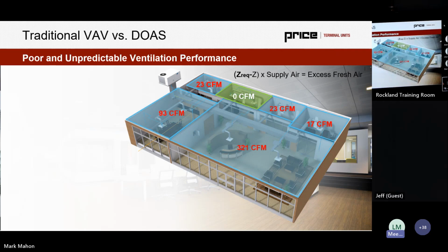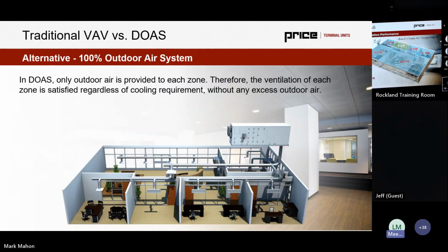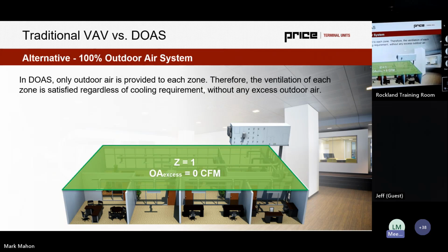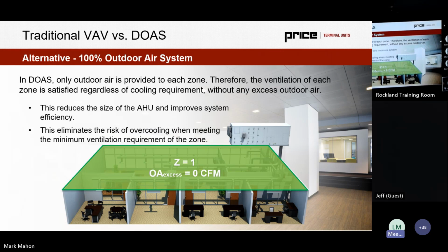Now, it's also possible instead, rather than excess fresh air, if the system was balancing correctly, you could have a lack of fresh air to certain zones. You could have a risk of maybe overcooling internal zones in this case as well. But this is ASHRAE's rationale and where it comes from. And so from their viewpoint, the alternative being 100% outdoor air, that means we're only providing outdoor air to each zone. Therefore, the ventilation of each zone is satisfied regardless of the cooling load. That decoupling of ventilation and latent versus sensible means that we can hit ventilation and latent perfectly on the nose. However, of course, it does beg the question, how are we going to cool the zone sensibly instead?